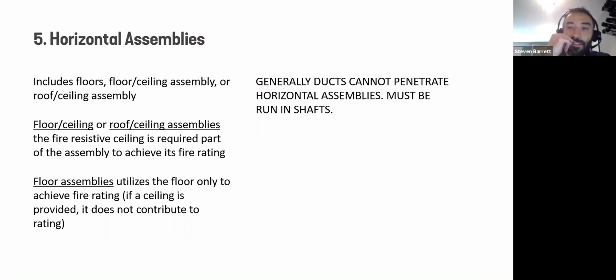Now, horizontal assemblies. This is kind of a fancy word, but it refers to floors, floor ceiling assemblies, or roof ceiling assemblies. Generally speaking, ducts cannot penetrate horizontal assemblies. Just as a general rule, your ducts need to run in shafts. But there are a few cases when a duct can penetrate a floor, for example. So we'll get into those.